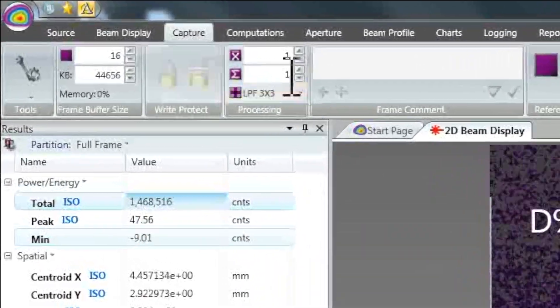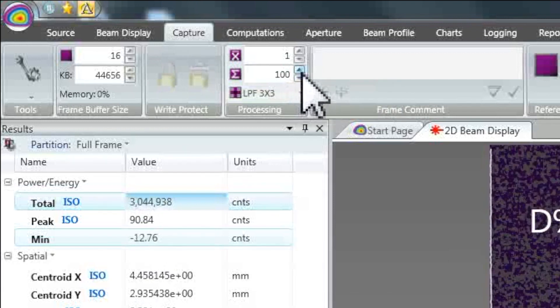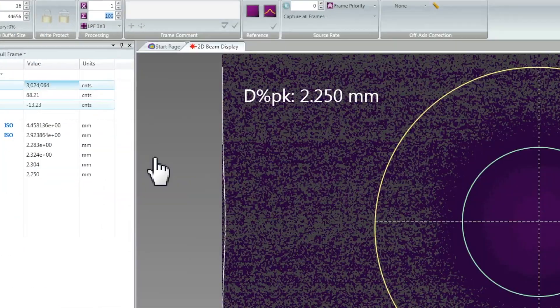BeamGage offers a feature called frame summing. This allows a select number of frames to be compiled or summed to build up the image to one that is visible, yet still representative of the laser source beam.